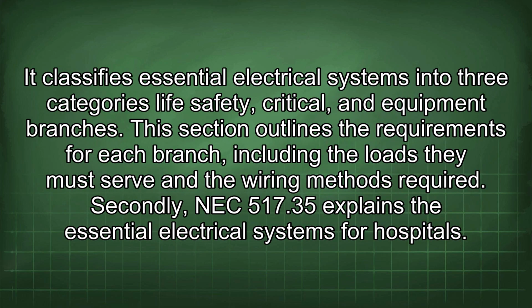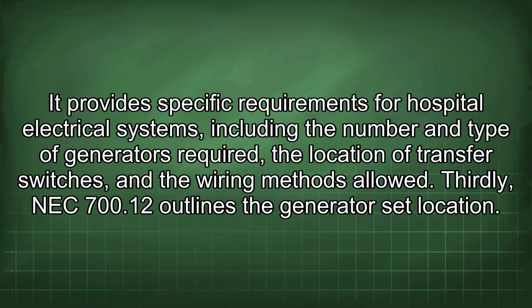It classifies essential electrical systems into three categories: life safety, critical, and equipment branches. This section outlines the requirements for each branch, including the loads they must serve and the wiring methods required. Secondly, NEC 517.35 explains the essential electrical systems for hospitals. It provides specific requirements for hospital electrical systems, including the number and type of generators required, the location of transfer switches, and the wiring methods allowed.